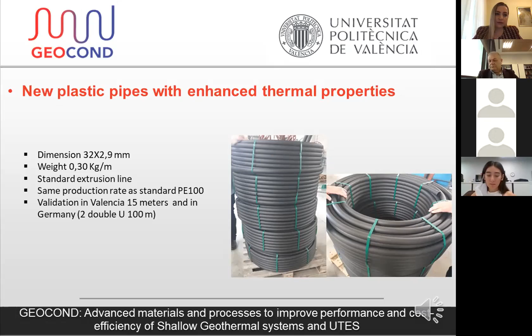The mechanical properties are similar to standard PE100, but the thermal properties are widely better — around 1 watt per meter-Kelvin compared to the standard of about 0.40 to 0.42, so we are more than doubling the current thermal property value. The produced pipe was tested in Valencia with very good results, and now we are installing it in Germany with different configurations: single U, double U, coaxial, etc. We are very happy and proud of this result, because overall the installation can be greatly enhanced through the combination of these different solutions.